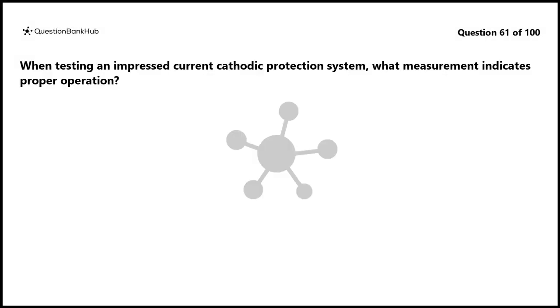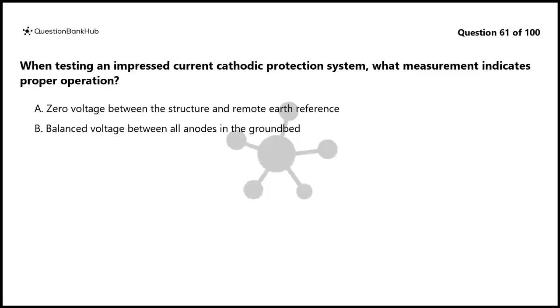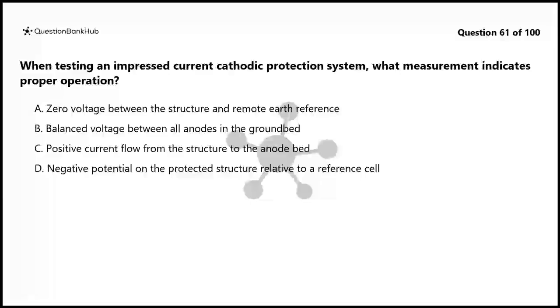Question 61. When testing an impressed current cathodic protection system, what measurement indicates proper operation? A. Zero voltage between the structure and remote earth reference. B. Balanced voltage between all anodes in the ground bed. C. Positive current flow from the structure to the anode bed. D. Negative potential on the protected structure relative to a reference cell.